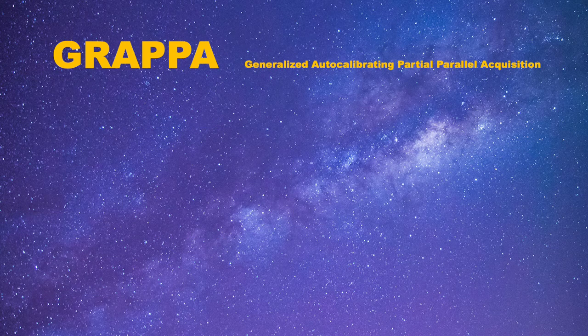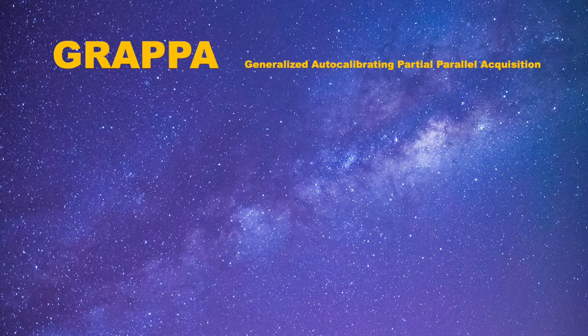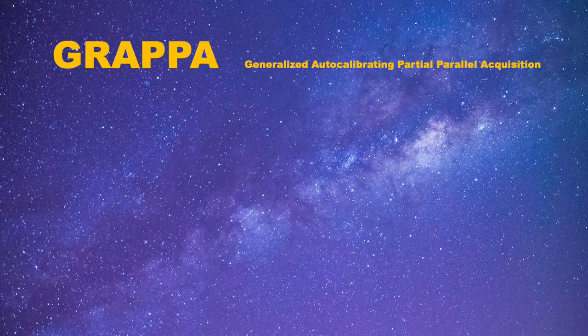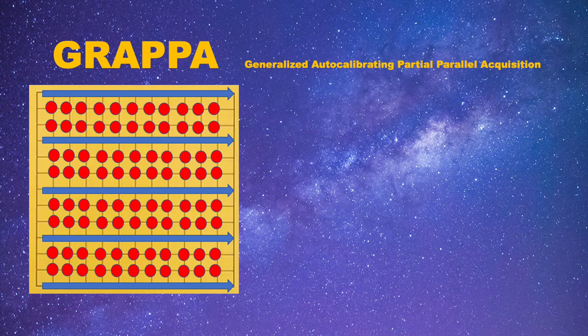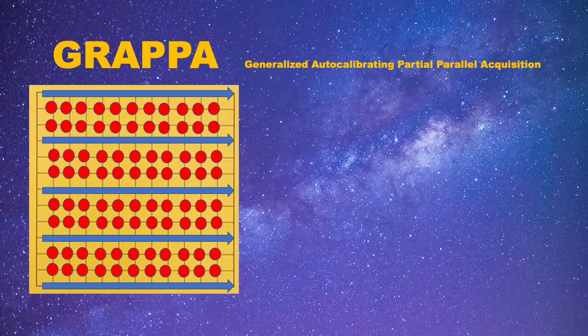Next, let's talk about another method called GRAPPA. Its full name is Generalized Auto-Calibrating Partial Parallel Acquisition. The idea behind this method is quite different from that of SENSE. It doesn't use sensitivity information to reconstruct the image, but it works by filling the missing points in the k-space. This step is just like filling a Sudoku where you have parts of the known information, and you try to fill the missing numbers with the rule and known information. In this way, we can get the complete k-space and our images are no longer aliased.